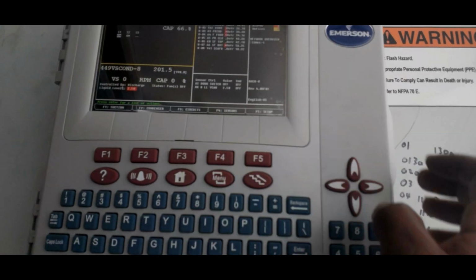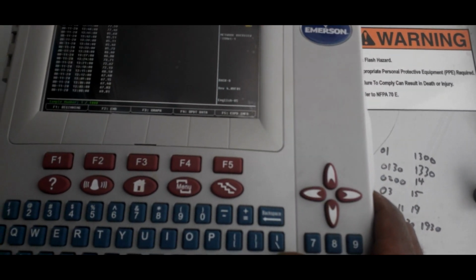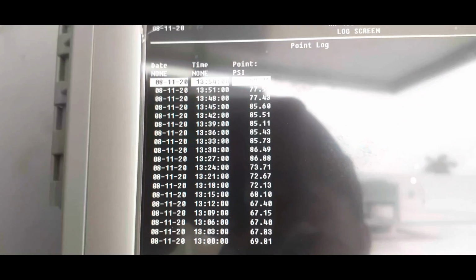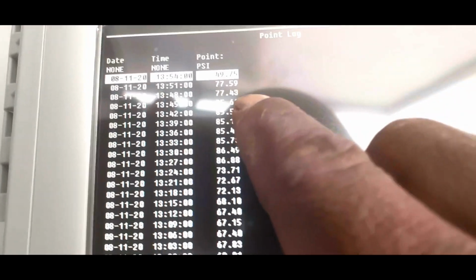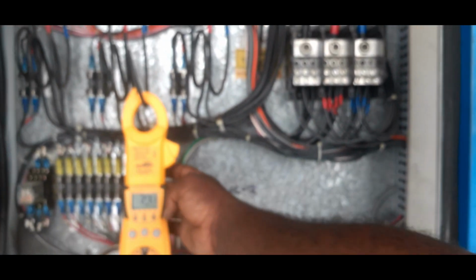Look at that. We went from 63 to 49 that fast. All I did was close that ball valve. So look, 77. Went from 77 to 49. All I did was close that hot gas solenoid. So now we should be coming down to meet rack suction set point. Compressor 2 just pulled in right now. What's that? 26 amps. So we're running there.